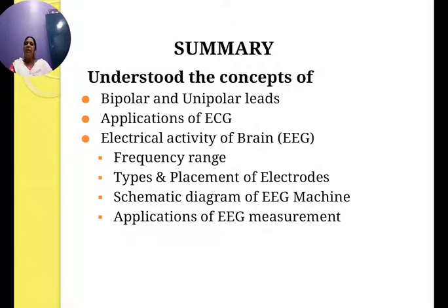The montage selector is a large panel containing switches that allow the user to switch electrode pairs and select the desired electrode pairs. Then we have the preamplifier. Every channel has an individual multi-stage AC coupled, very sensitive amplifier with differential input and adjustable gain in a wide range. Its frequency response can be selected by single stage passive filters.